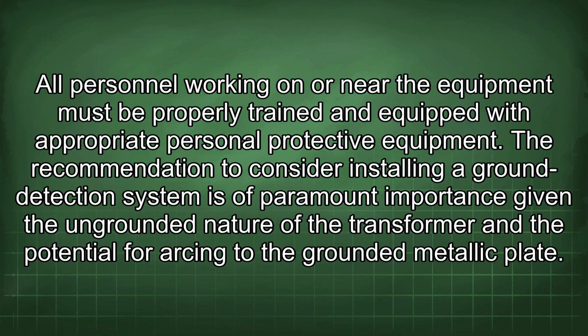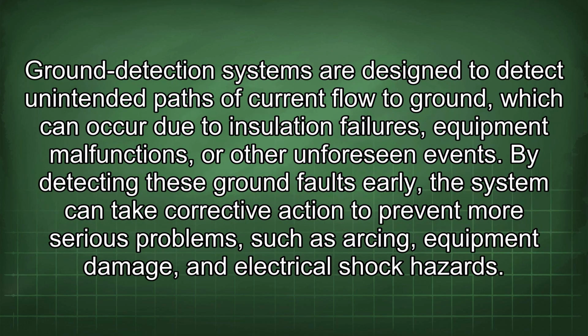The recommendation to consider installing a ground detection system is of paramount importance given the ungrounded nature of the transformer and the potential for arcing to the grounded metallic plate. Ground detection systems are designed to detect unintended paths of current flow to ground, which can occur due to insulation failures, equipment malfunctions, or other unforeseen events. By detecting these ground faults early, the system can take corrective action to prevent more serious problems such as arcing, equipment damage, and electrical shock hazards.